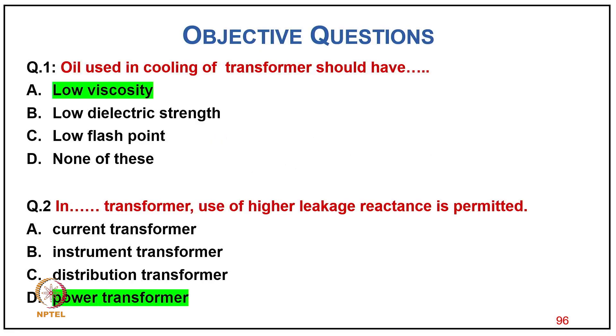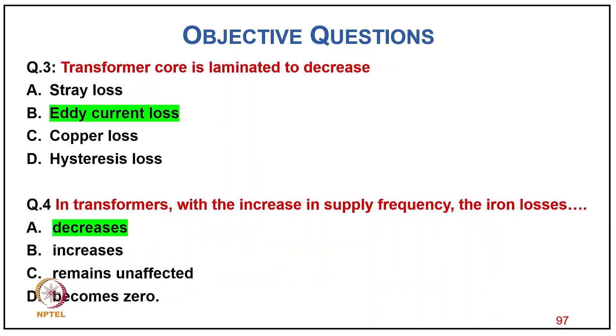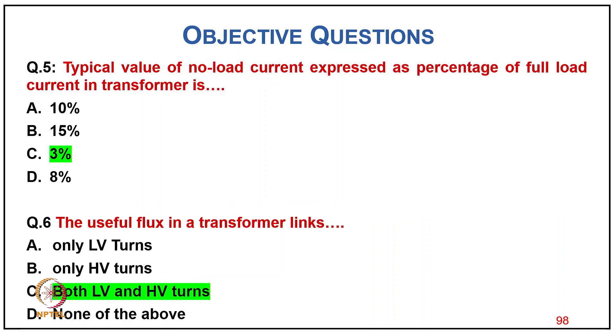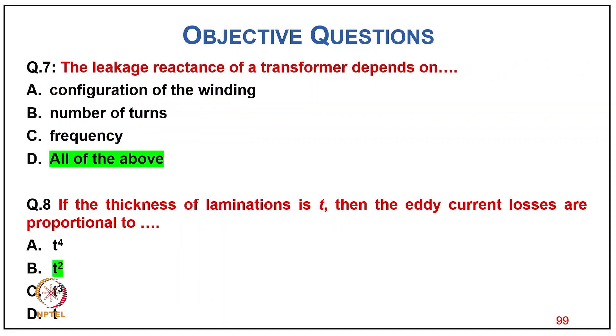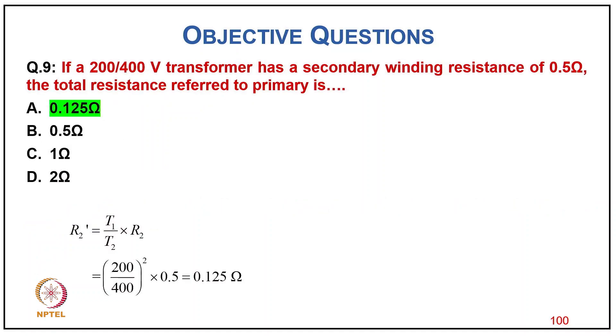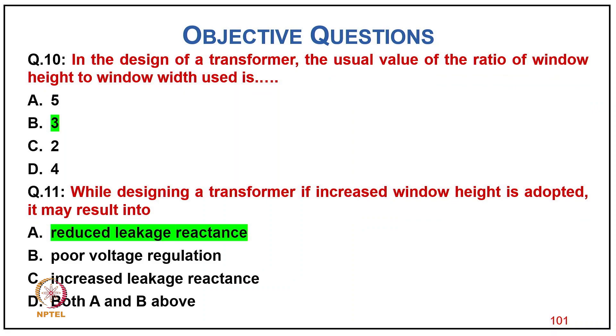Objective questions: Oil used in cooling transformers should have low viscosity. Power transformers use high leakage reactance. Transformer core is laminated to decrease eddy current losses. With increase in supply frequency, hysteresis losses decrease. Typical no-load current is about 3% of full load current. Useful flux in a transformer links both LV and HV turns. Leakage reactance depends on configuration of winding, number of turns, frequency, and lamination thickness t — eddy current losses are proportional to t². For a 200/400 V transformer with secondary winding resistance of 0.5Ω, the total resistance formula applies. The usual ratio of height to width of window is 3. Increased window height adopted may result in reduced leakage reactance.